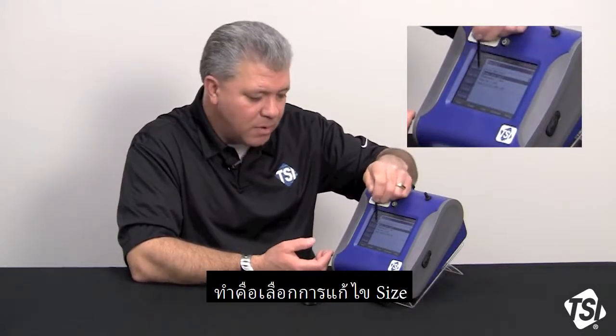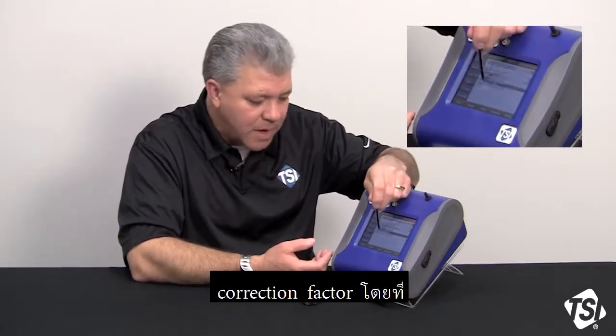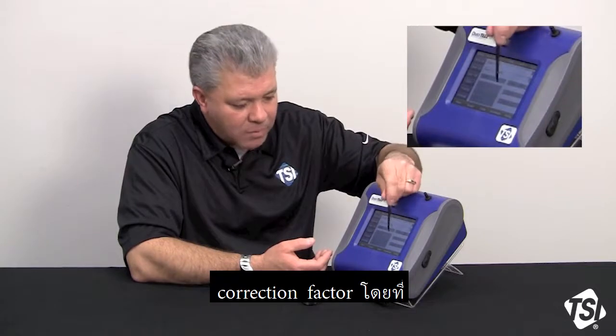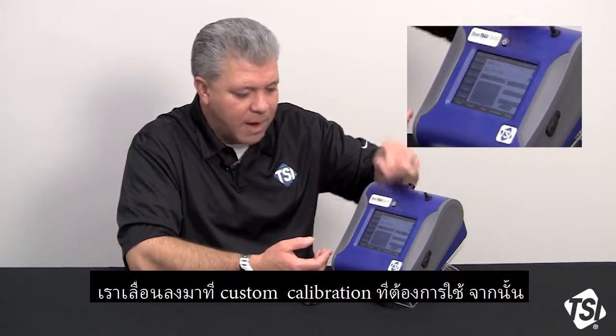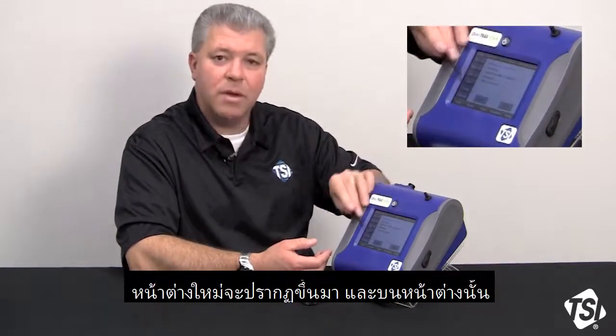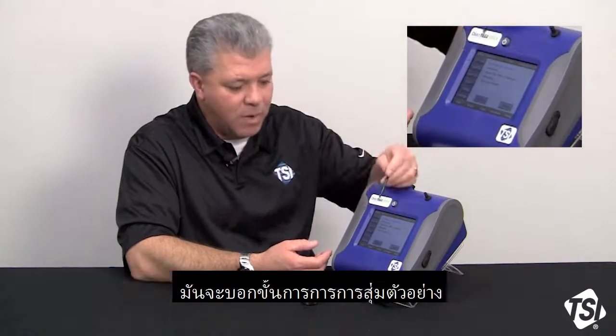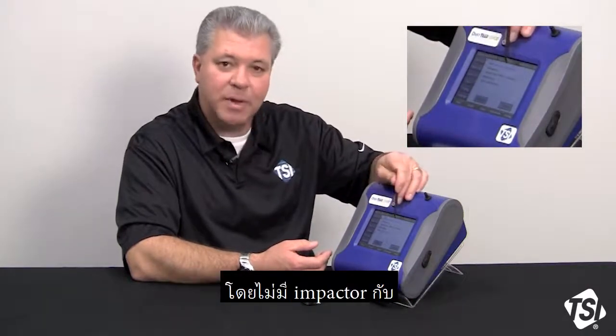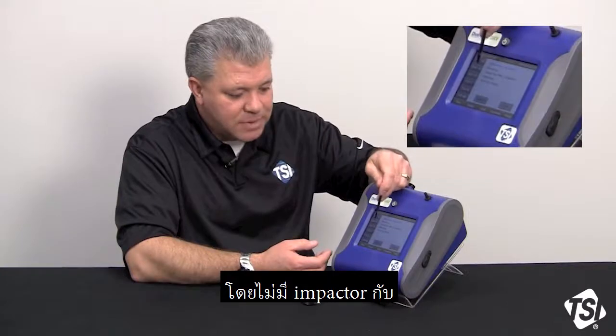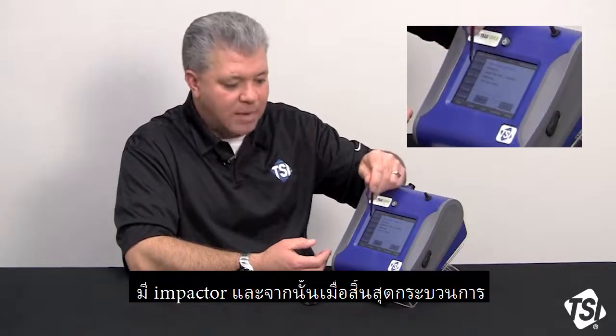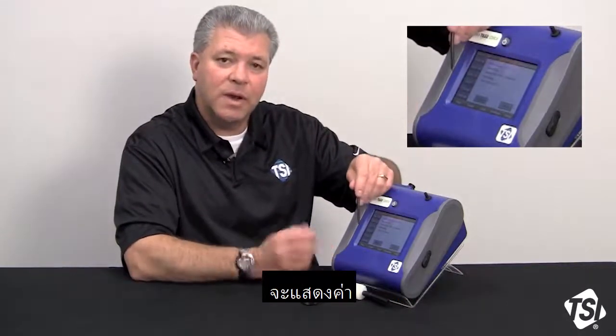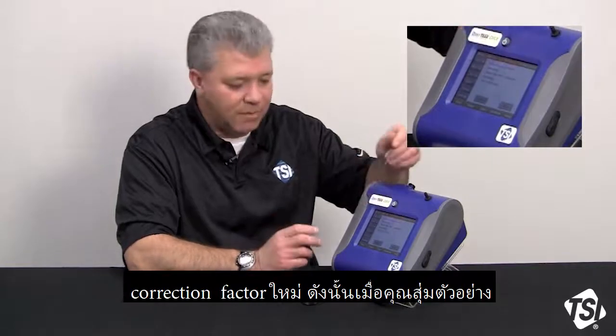So what we're going to do is select size correction factor, and we're going to come down here to custom calibration. A new window will pop up, and on that window it's going to say sampling without an impactor, sampling with an impactor, and then at the end of the procedure it will come up with a new correction factor.